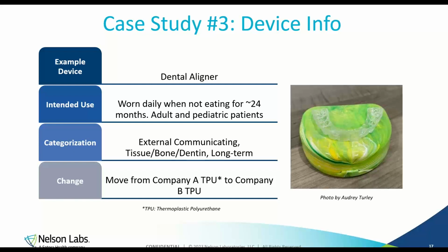So if we really look at the mucosal membrane category contact for long-term devices, and we compare the biological endpoints that are of concern to those for external communicating tissue long-term contacting devices, they're actually almost identical. The only difference is the requirement for a material-mediated pyrogen test in the external communicating category. But if you actually look at some of the other government regulatory bodies like FDA, they actually want you to include the material-mediated pyrogenicity in there anyways. So very similar, and I picked the escalated category, which is our external communicating tissue bone dentin long-term category. So just an example of how we can settle some of those disputes to make sure we start on a clear path for our risk assessment.